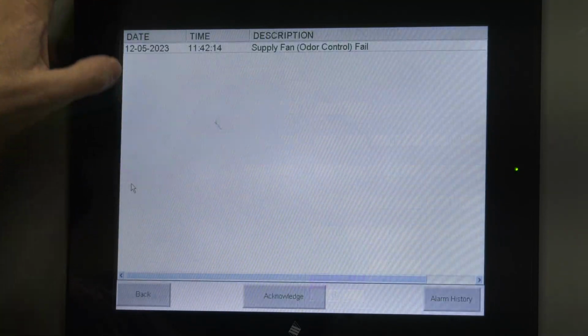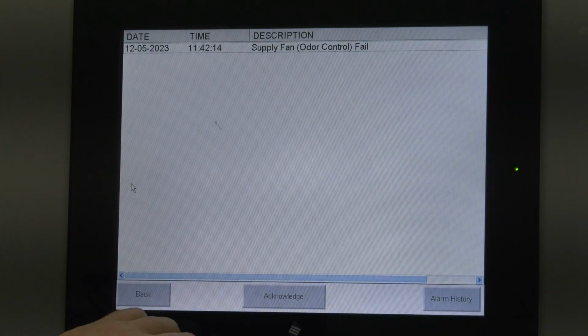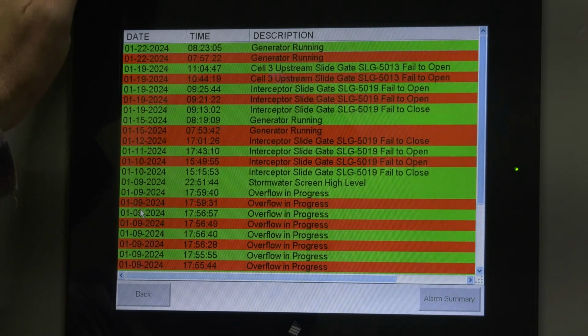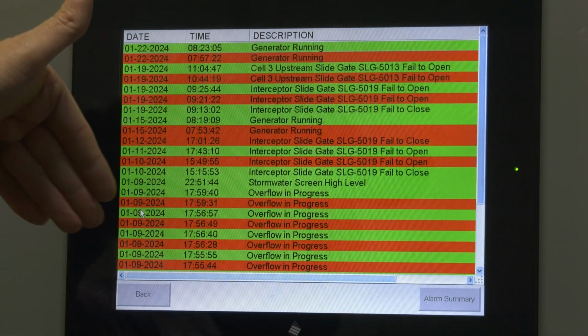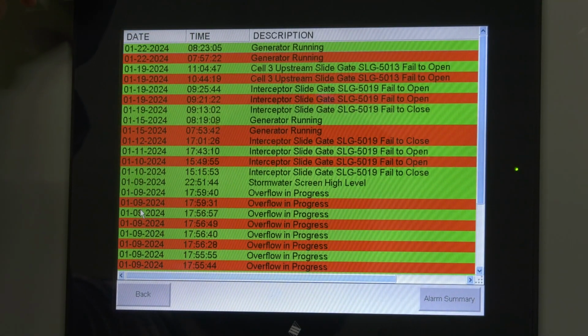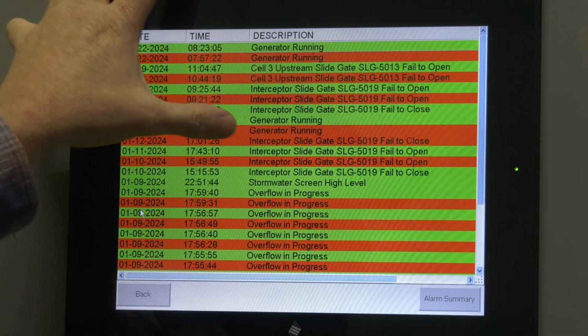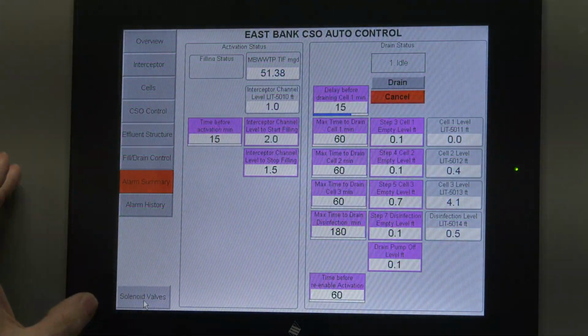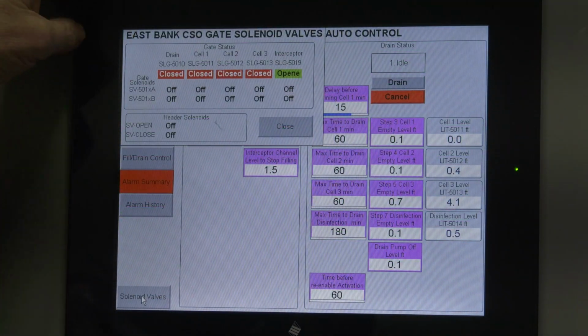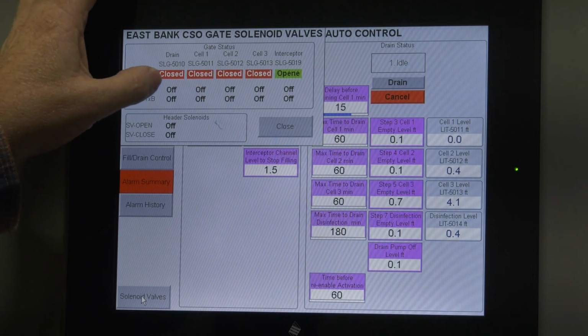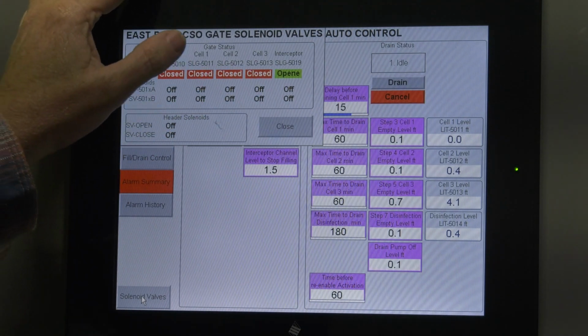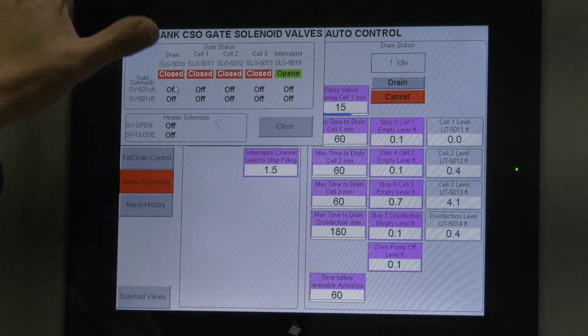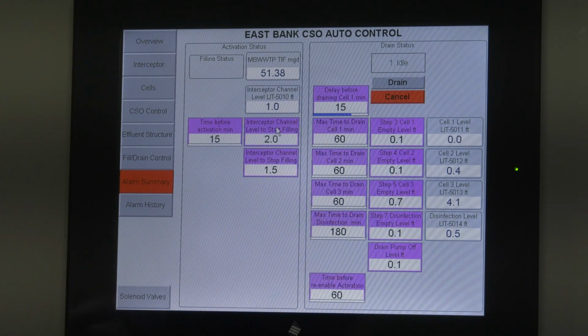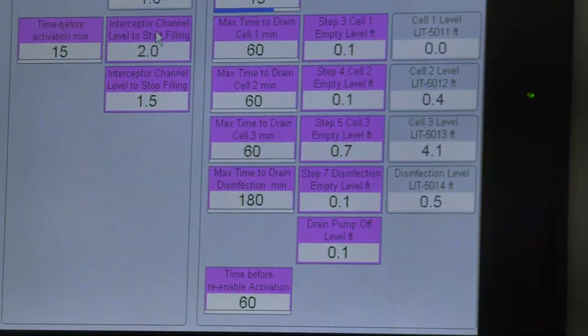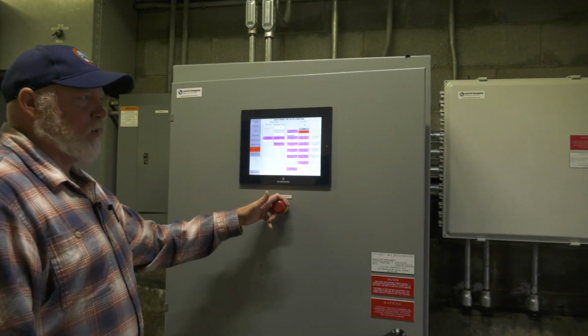Alarm summary is going to give you current alarms. Alarm history is going to give you all the history of any alarm you had. Green means it's been acknowledged or the alarm no longer exists. Red means it's current. And the solenoid screen, you'll see where it currently says off, it'll change to on if the solenoid's on. And this is a good tool for troubleshooting or to see what step you're on. All right, we've got an emergency call button on the front.